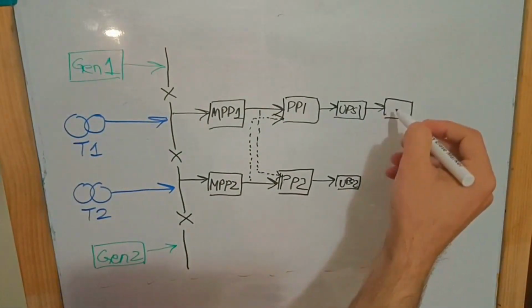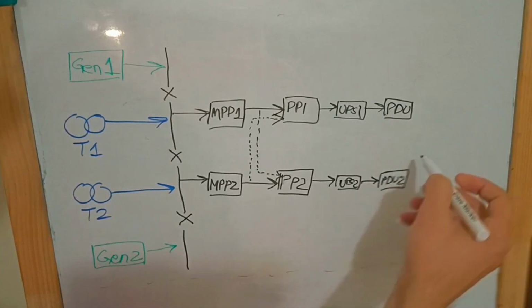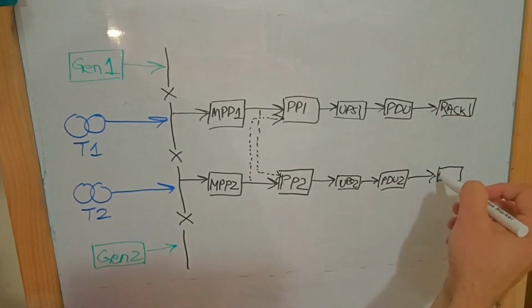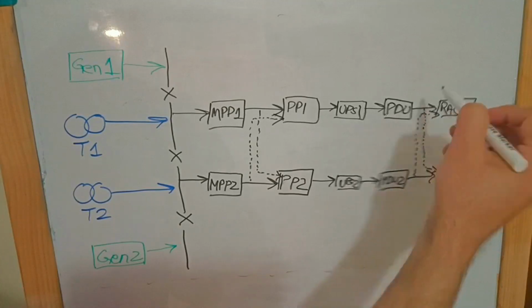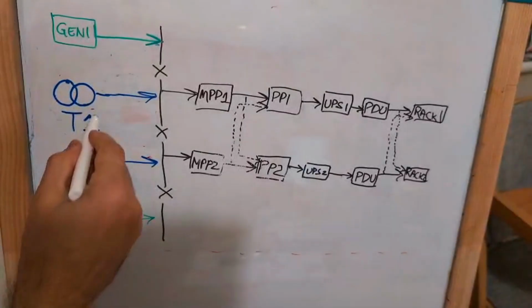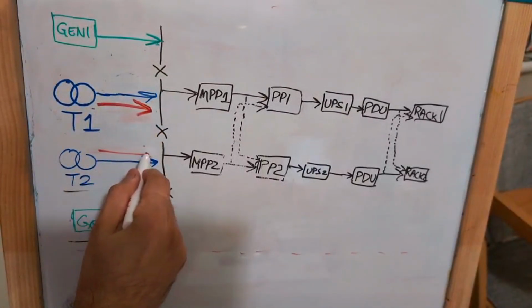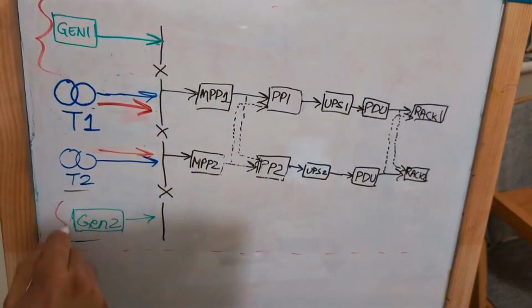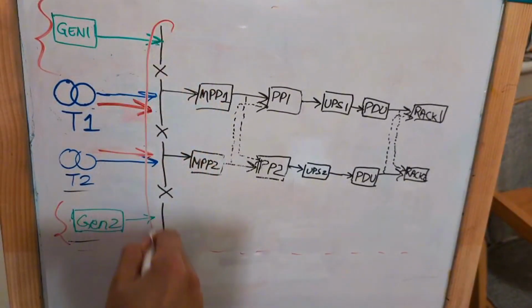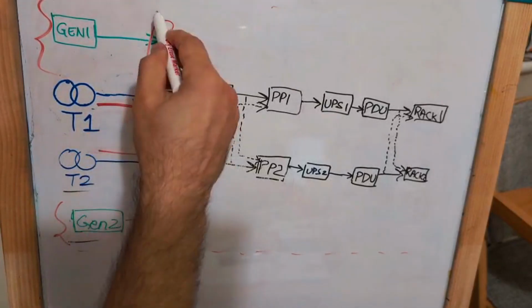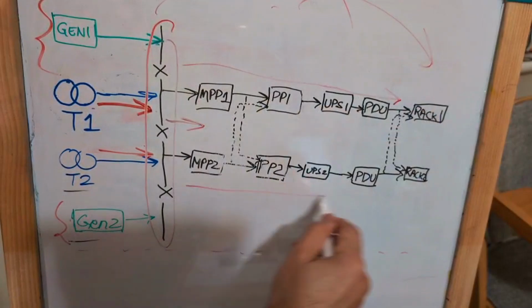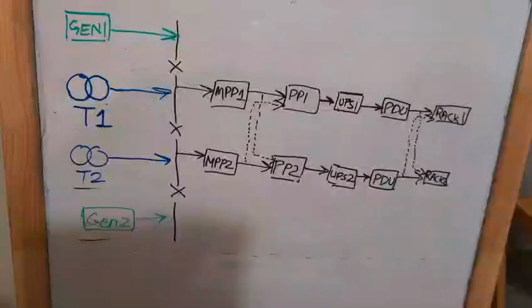Alright squad, let's zoom out and see what's actually powering these data centers, because trust me, it's not just one fat cable and a prayer. You've got your general transformers supplying the primary power and massive generators as the backup, both pushing power through the thick bus bars and cables. All this incoming power doesn't go straight to the servers, no. It flows into a whole row of industrial grade UPS systems.